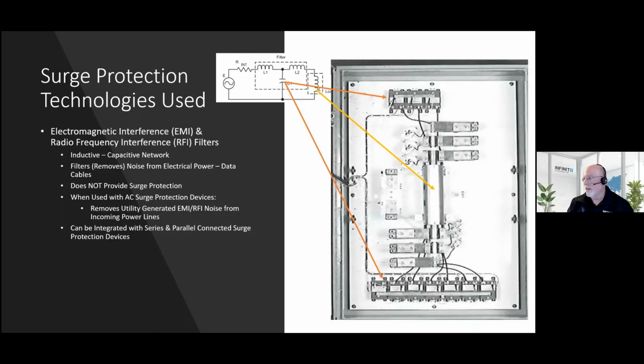And in this case, what we're looking at here is a series connected surge protection device. And what these arrows point to is the inductive-capacitive EMI RFI filter network built into this thing. So here's the coil, and then these cans up here and down here are the capacitors in the filter network, removing EMI and RFI off of the incoming utility power line. So broadcast loves this just for that reason. If you can remove noise from the AC, you don't have to work so hard after the main breaker and with all your other equipment to remove noise. So why is this here? We'll get to that in the question section later, but it's also a good visual to show you that there are surge arrestors that are series connected as opposed to parallel connected. And series connected units will usually have a nice filter network shown schematically here.